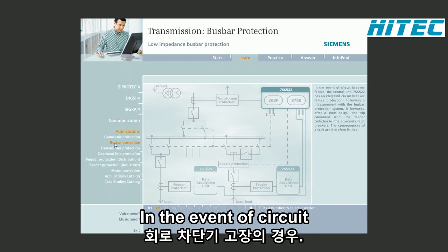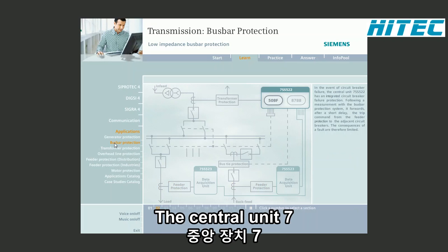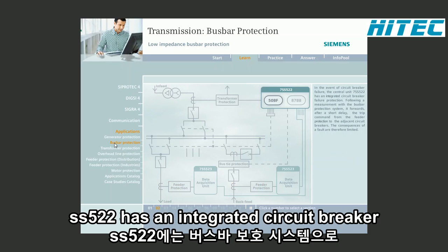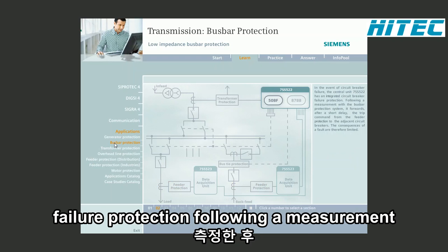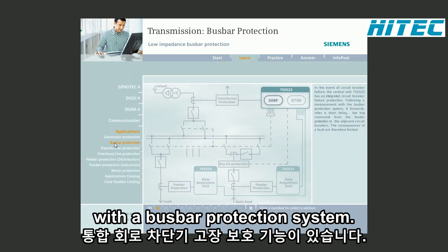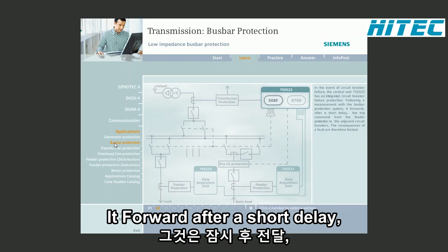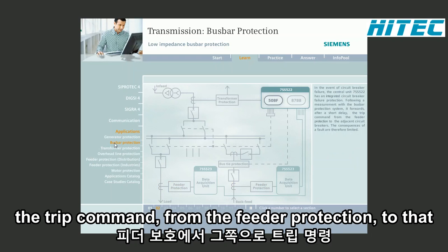In the event of circuit breaker failure, the central unit 7SS522 has an integrated circuit breaker failure protection. Following a measurement with a busbar protection system, it forwards, after a short delay, the trip command from the feeder protection to the adjacent circuit breakers. The consequences of a fault are therefore limited.